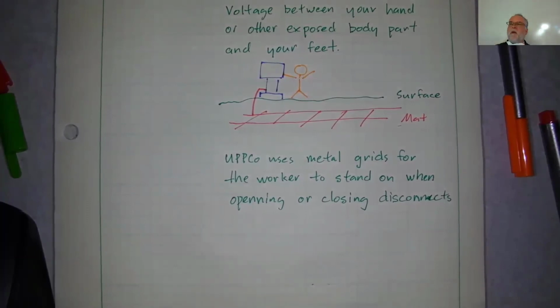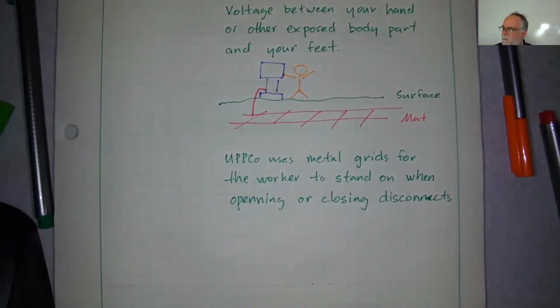Same thing with the ground grid. You can calculate for just little tiny segments of the ground grid what the step potential would be, and then it'll calculate it over the entire ground grid. That's why it takes a computer program, because you have this really fine set of triangles that you're calculating the voltage at every one of. Does that make sense?